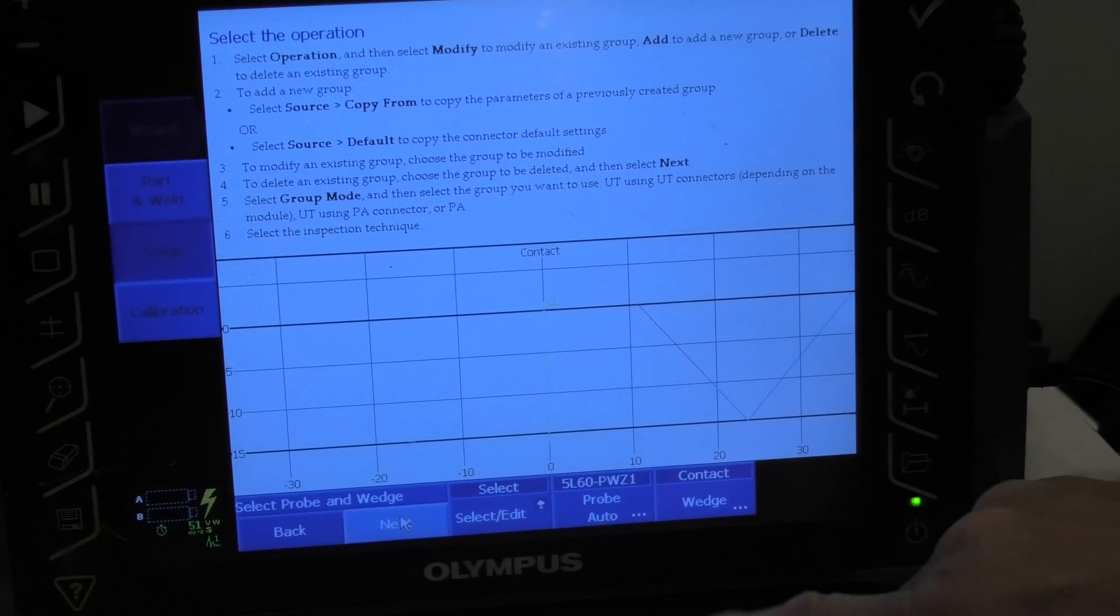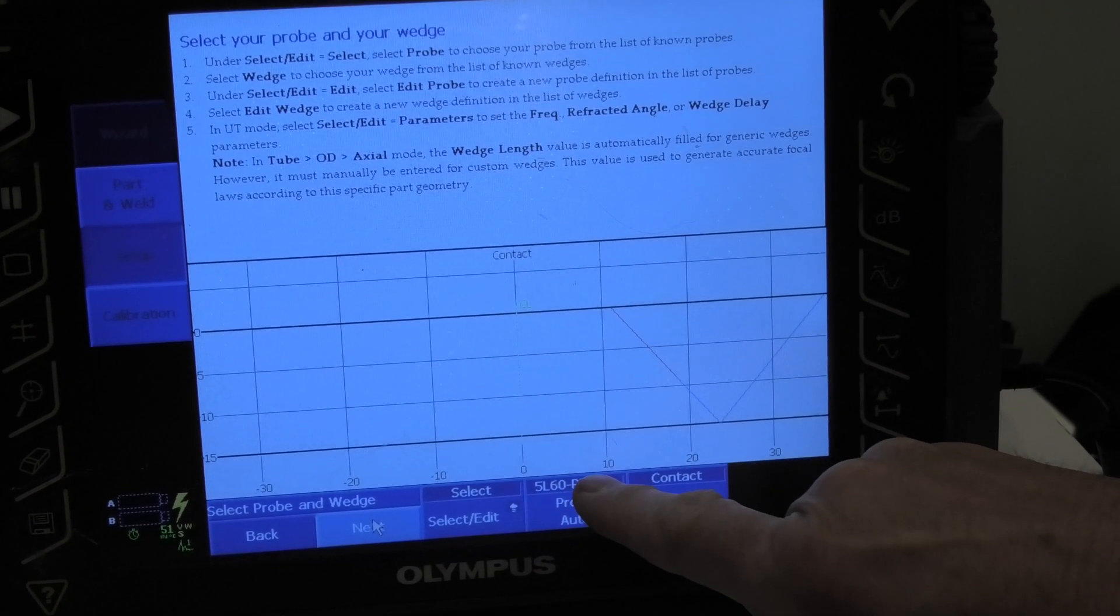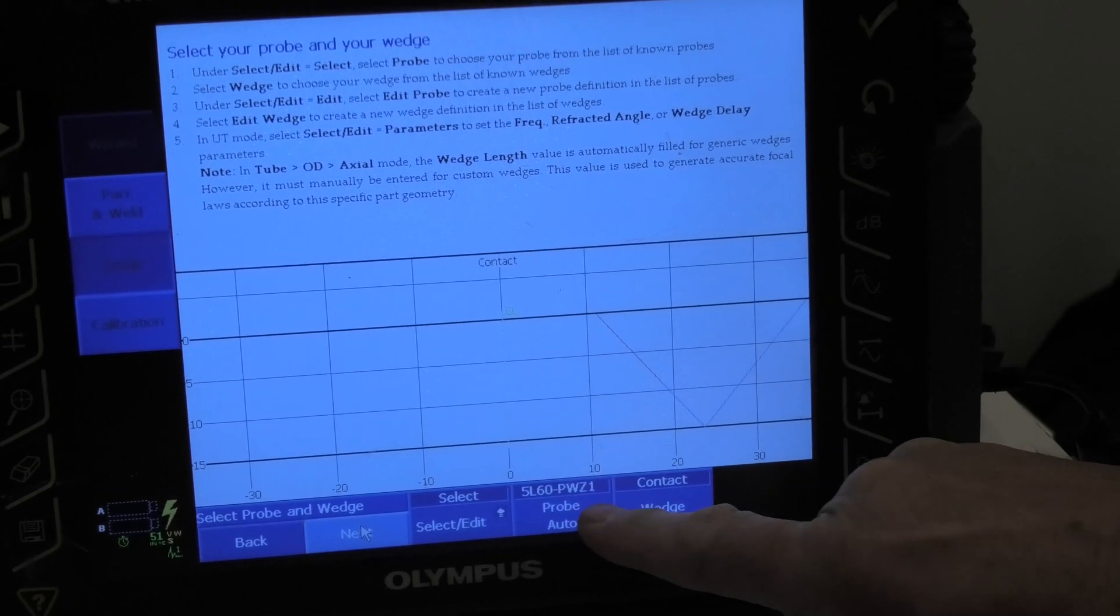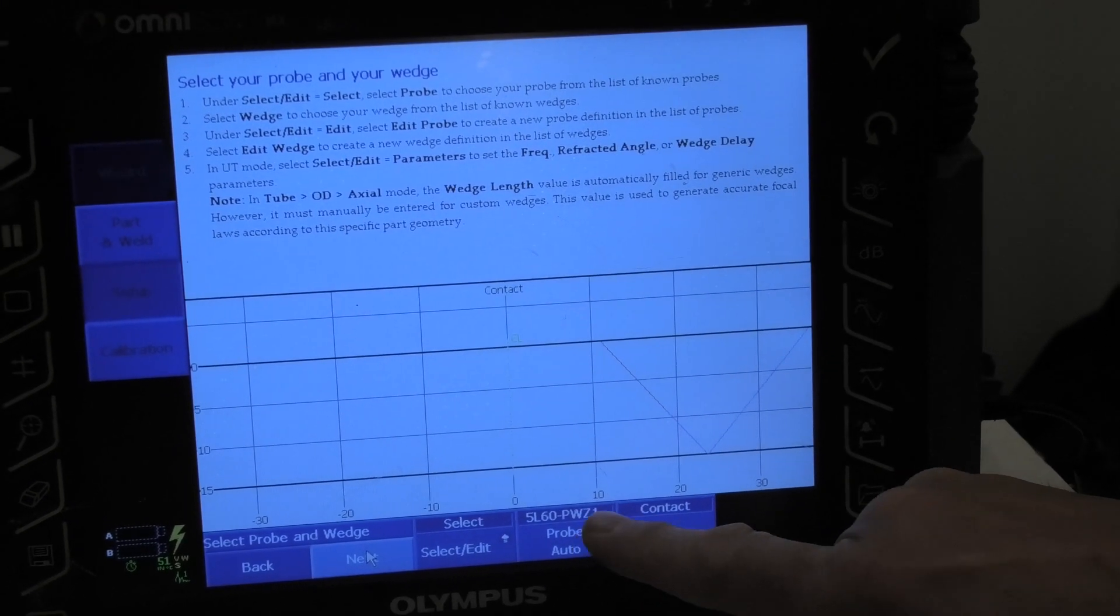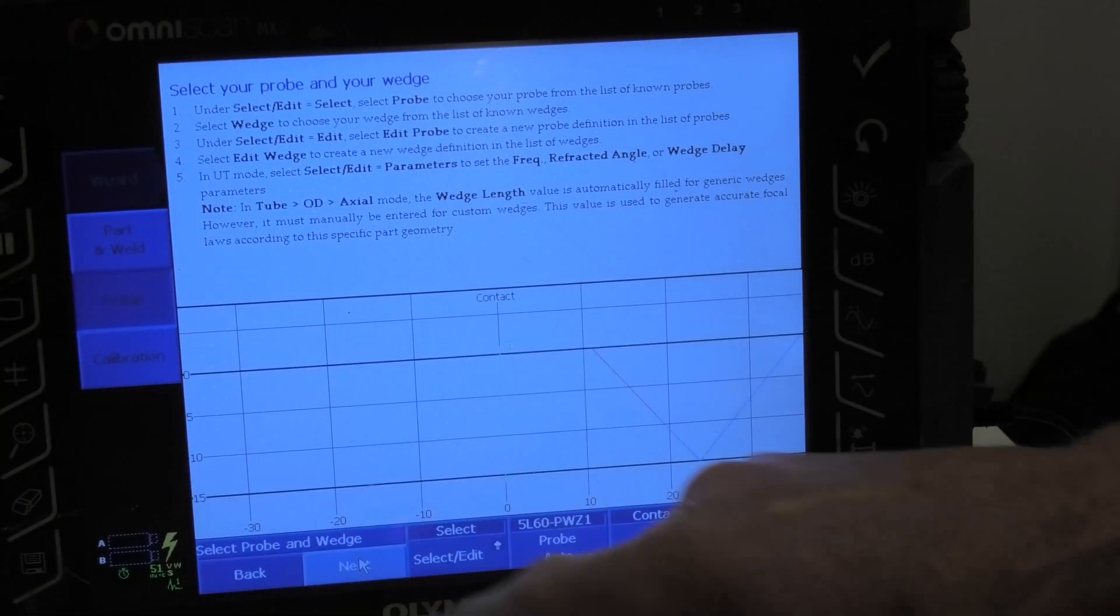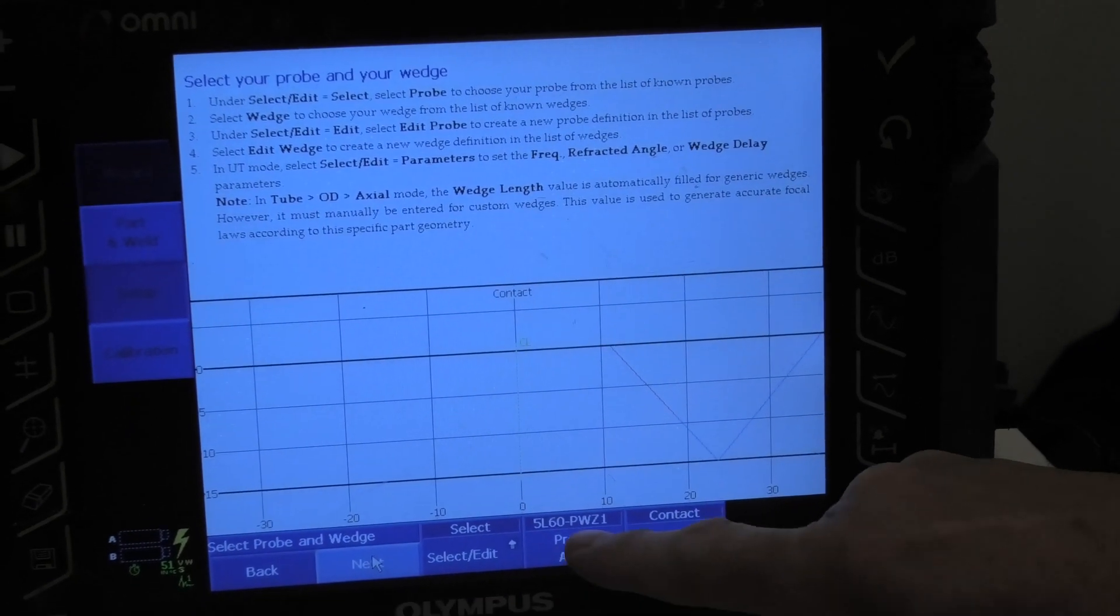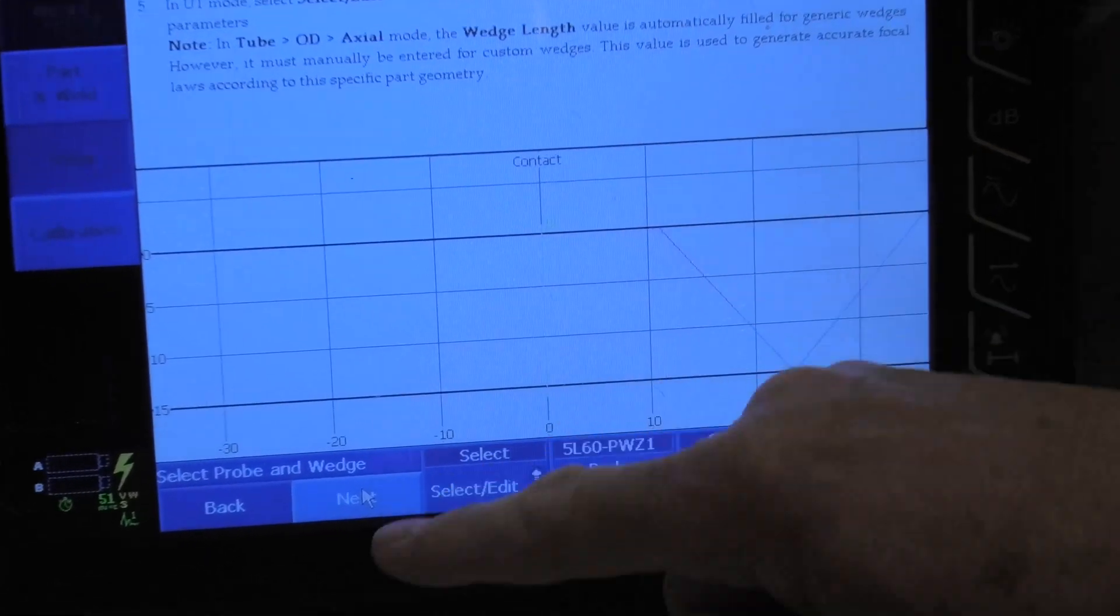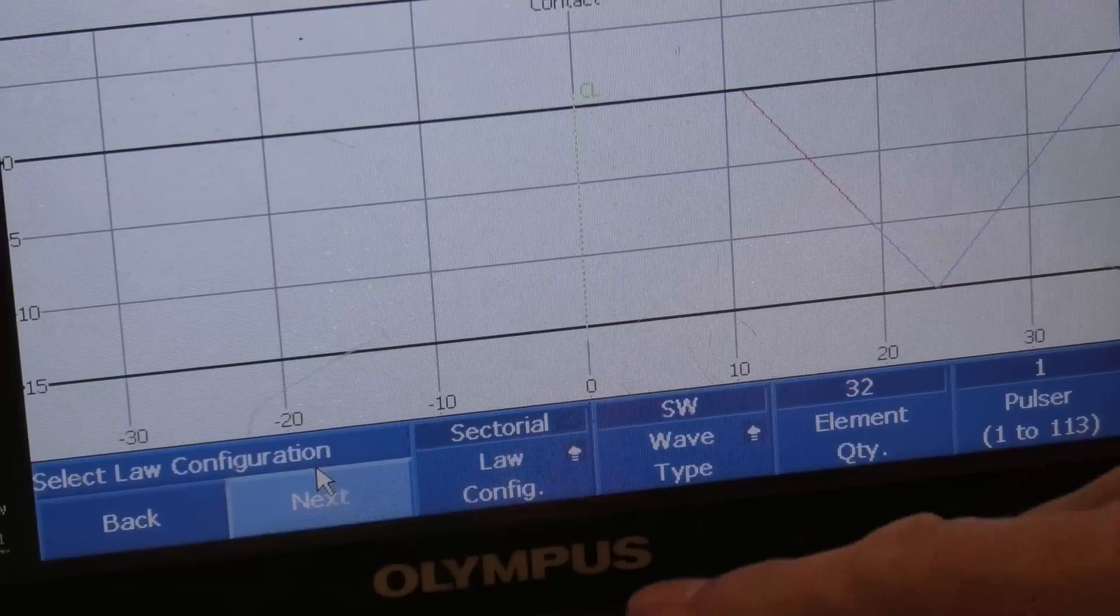Now what should have happened is the probe should have been automatically identified. Now if it hasn't been automatically identified, there's an issue with your probe and you'll need to manually enter it. So just make sure this lines up with the probe. We hit next.